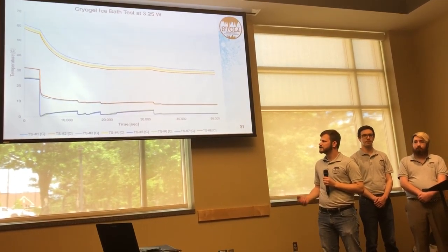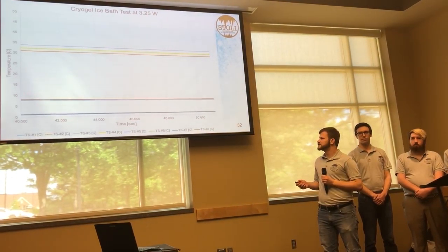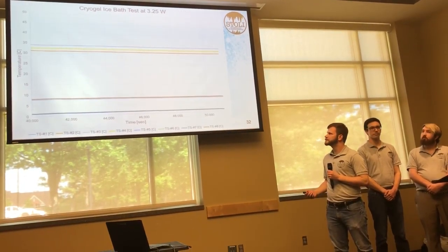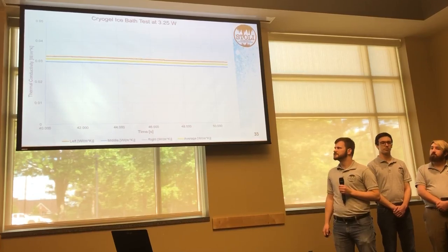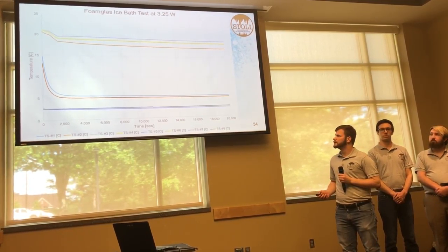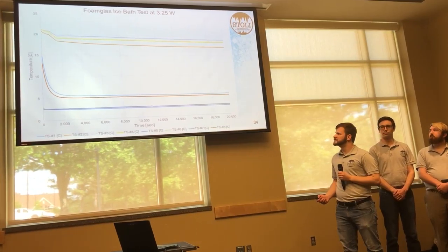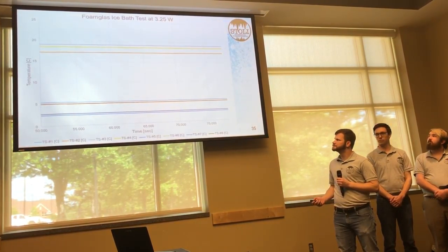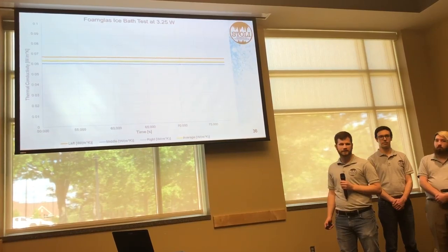This is our cryogel ice bath data. We got a temperature differential of about 30 degrees, with the end RTDs monitoring axial heat loss — we still had some. We got a thermal conductivity of about 0.032 on average, compared to the ideal value of about 0.018 for cryogel. We also did the ice bath test with foam glass, giving about a 15-degree delta T, with a measured thermal conductivity of about 0.063 compared to the ideal 0.04 for foam glass.